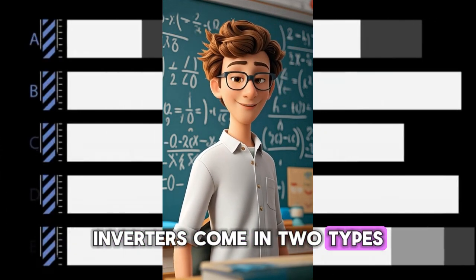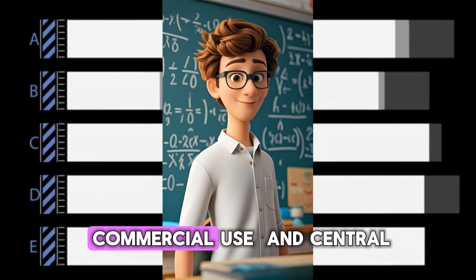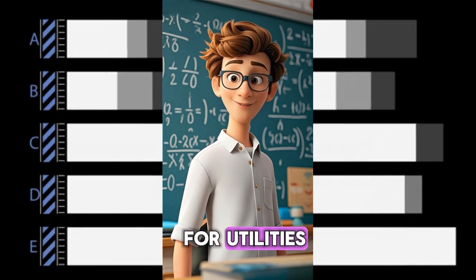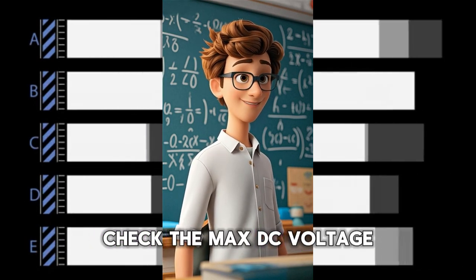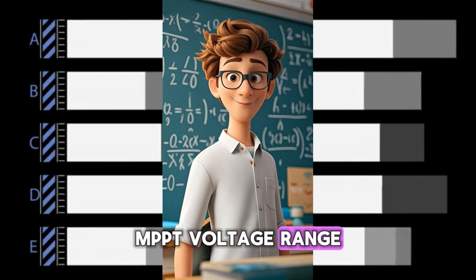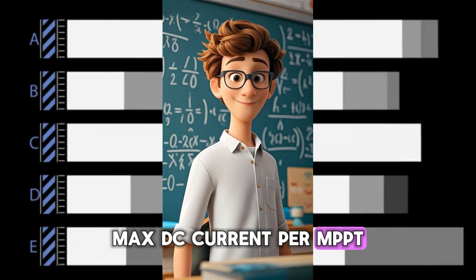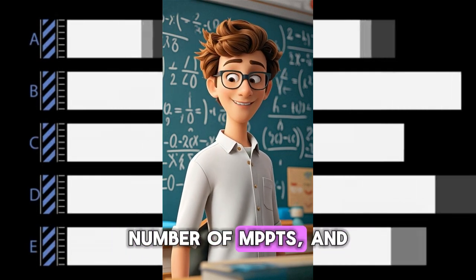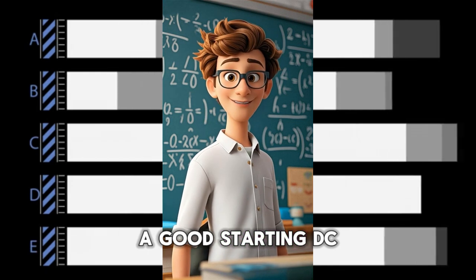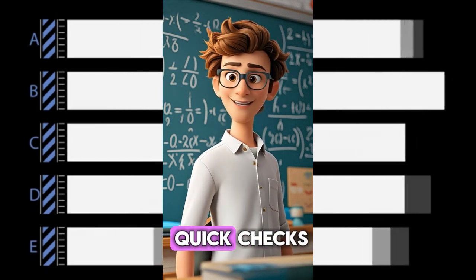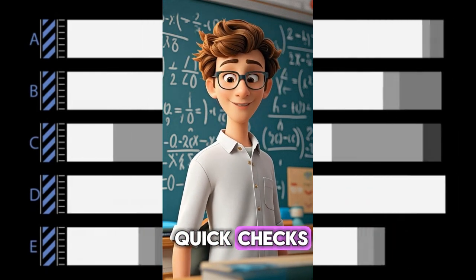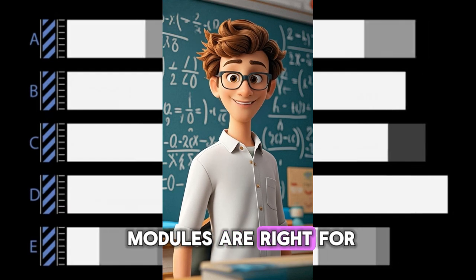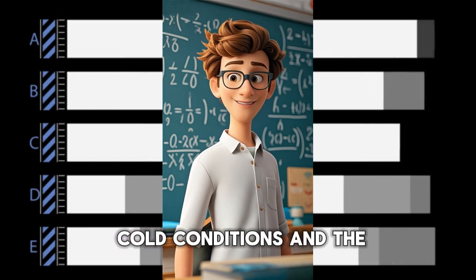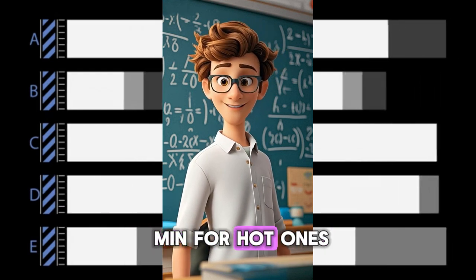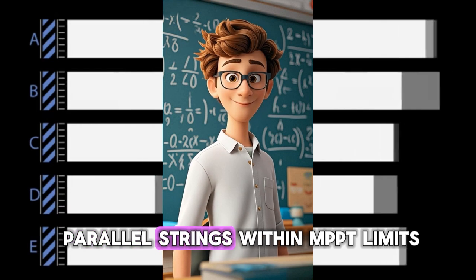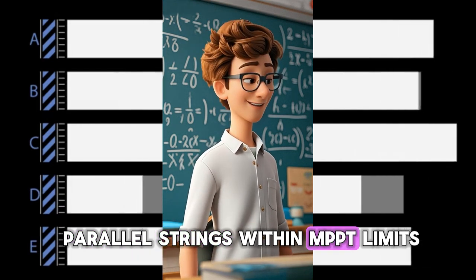Inverters come in two types: string, for homes and commercial use, and central, for utilities. Check the max DC voltage, MPPT voltage range, max DC current per MPPT, number of MPPTs, and AC power. A good starting DC-AC ratio is between 1.0 and 1.3. For quick checks, ensure the max series modules are right for cold conditions and the min for hot ones, while keeping ISC times parallel strings within MPPT limits.